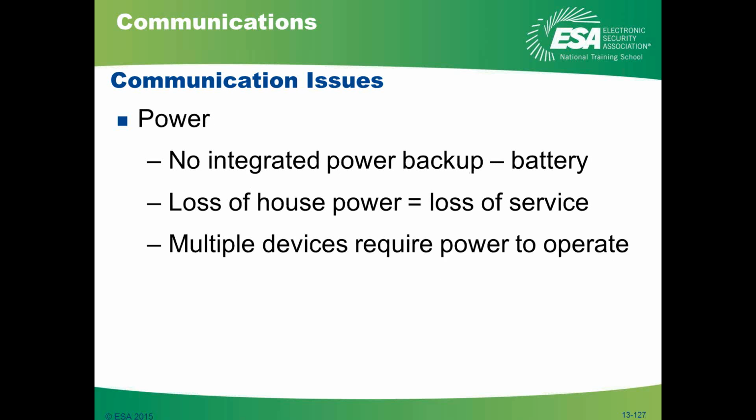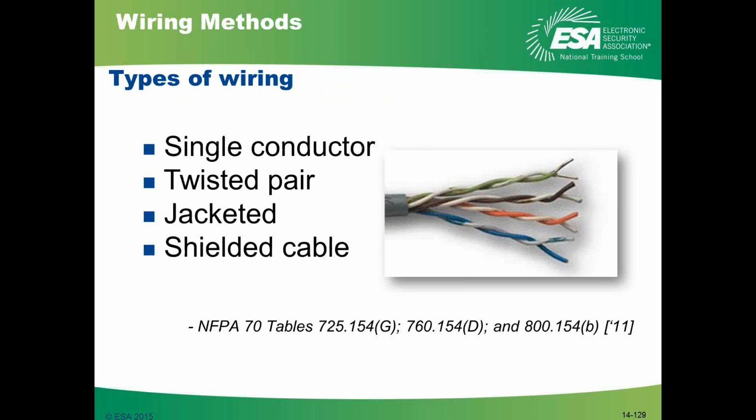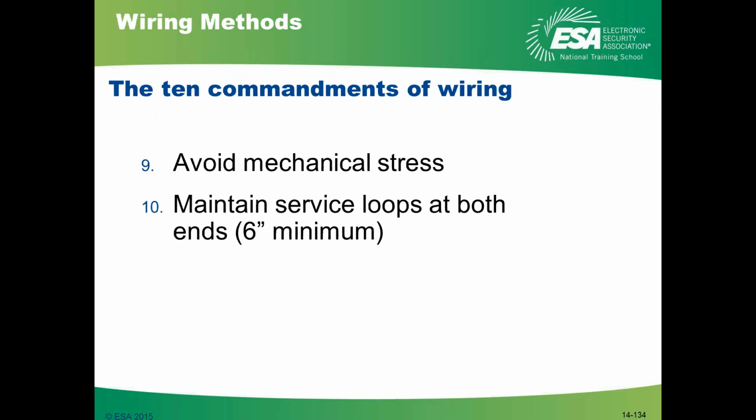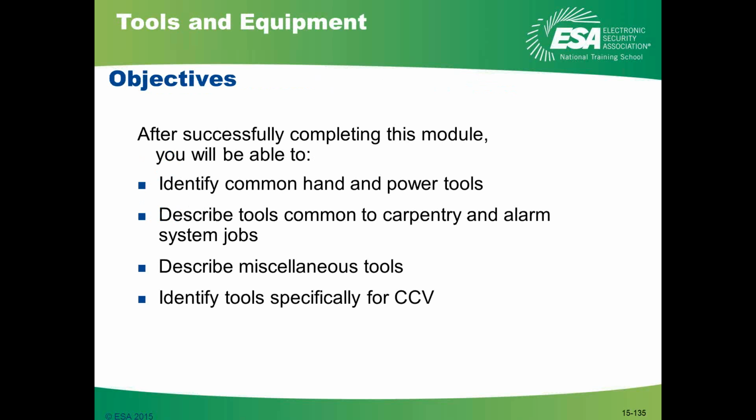And you'll see a lot of companies installing the RJ jack behind the small panel in the wall. Well, that violates this last 10 commandment that says it needs to be accessible, you know, the 6-inch minimum. It's a violation of the NEC. And I point that out to people that a lot of the way some of these systems were installed is a violation of the NEC and the FCC. So this is one of the things I bring out.